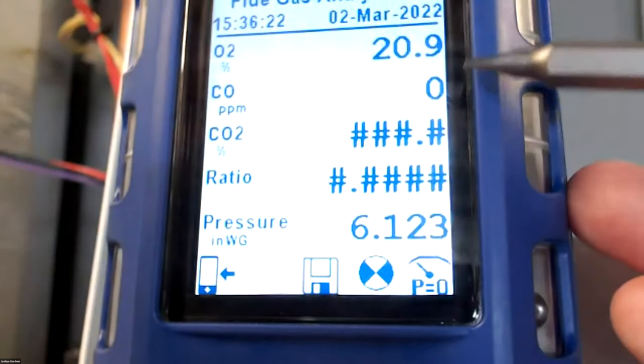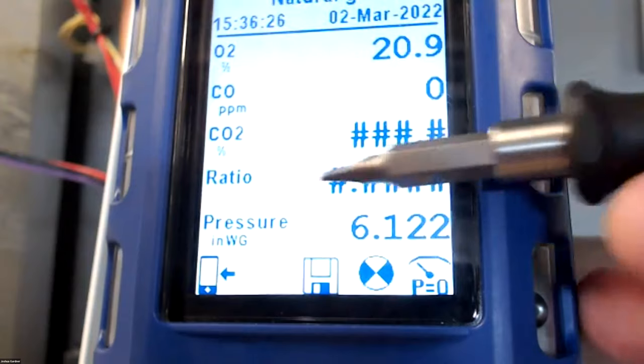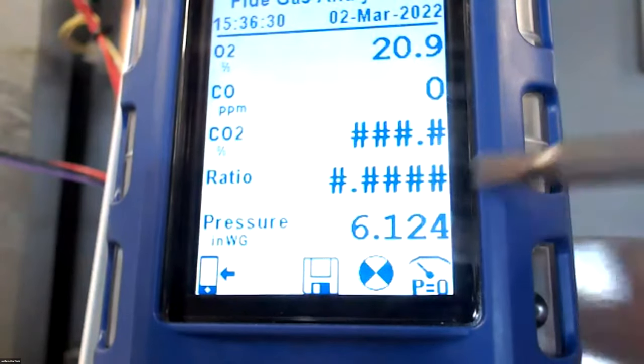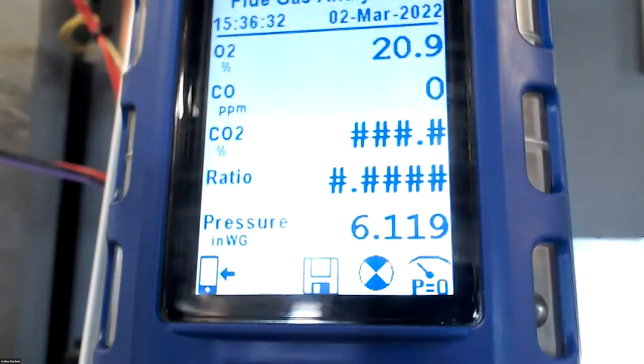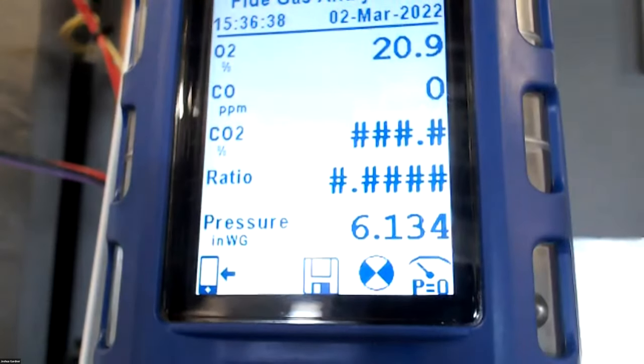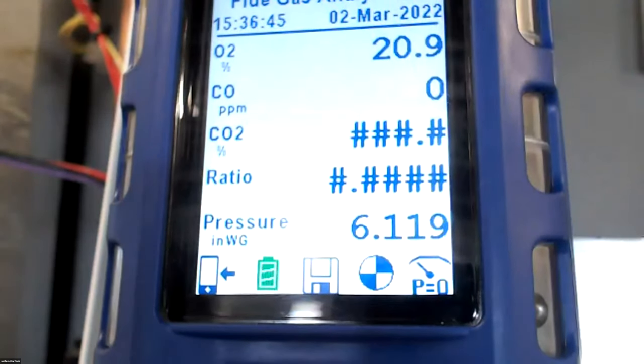All right, so my analyzer shows me my O2, my CO, my CO2, my ratio, which we don't use, and my gas pressure, all on one screen, which is really nice. Also, by pushing one button, I can send the report to an app as opposed to using a printer. So, got my probe in there, got my analyzer on. Go ahead and turn this thing on, dump some water here.